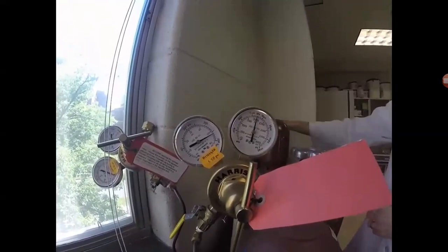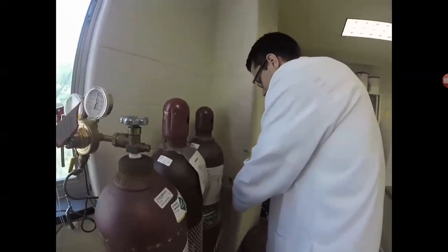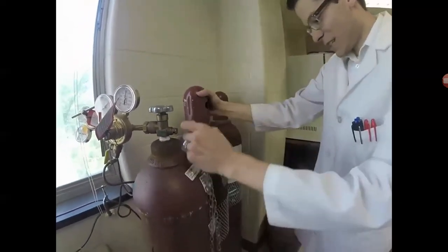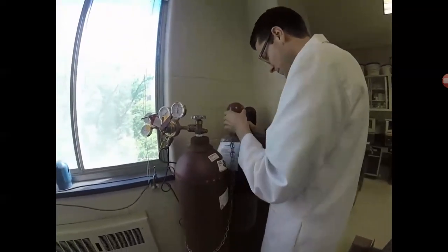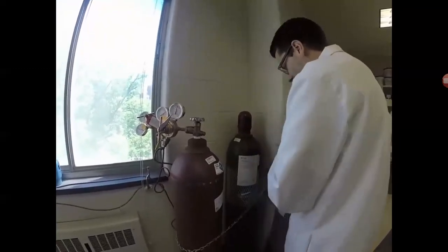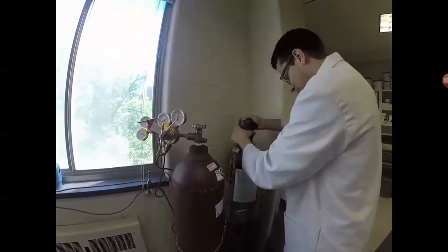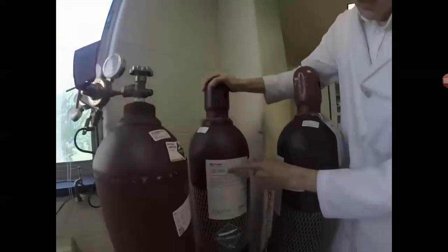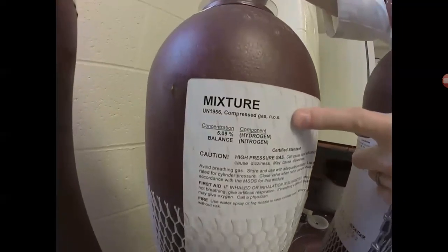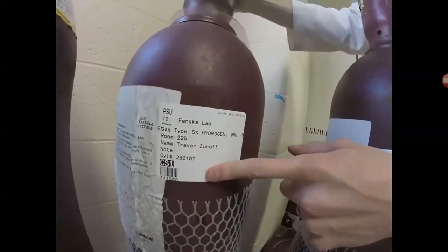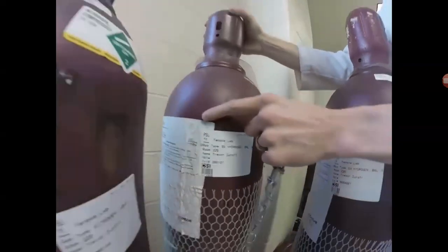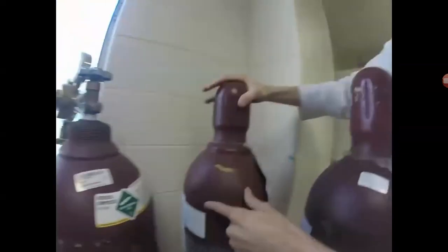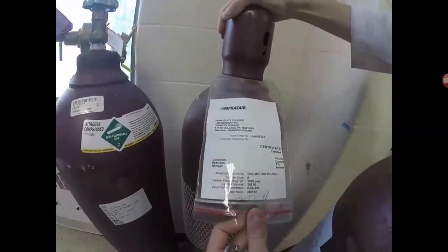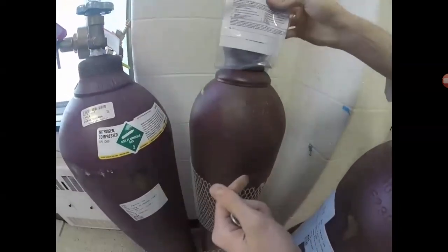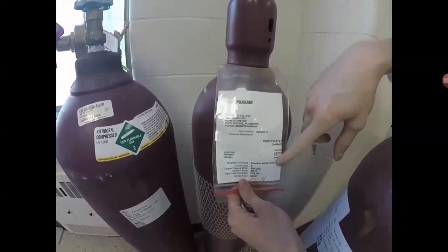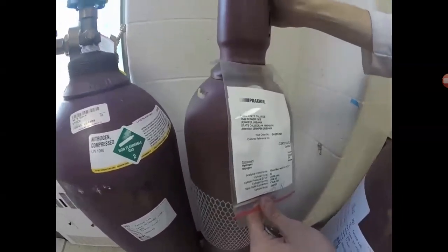So for the hydrogen nitrogen mix, I already have a new one sitting here. All we need to do is move it a little bit closer. Just make sure your cylinders are attached to the wall if you're moving them. Carefully. Okay, so you can show this too. If you're ever needing to know what's in there, you can always look on the label. It gives you nice information in terms of composition. Here it's also just a general type of cylinder, so it's 5% hydrogen. And then lastly, there's also this certificate of analysis that Praxair provides. Can't see it because it's all folded up, but in there it'll tell you not only the requested concentration, but the actual concentration, measured by, I think, a GC in this case.